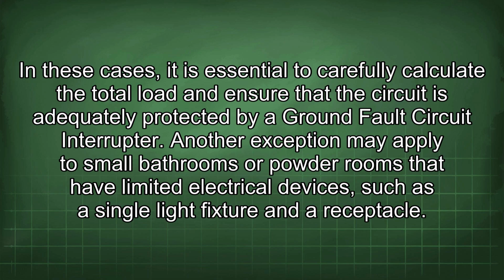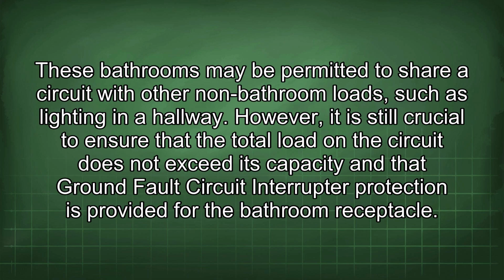Another exception may apply to small bathrooms or powder rooms that have limited electrical devices, such as a single light fixture and a receptacle. These bathrooms may be permitted to share a circuit with other non-bathroom loads, such as lighting in a hallway. However, it is still crucial to ensure that the total load on the circuit does not exceed its capacity and that ground fault circuit interrupter protection is provided for the bathroom receptacle.